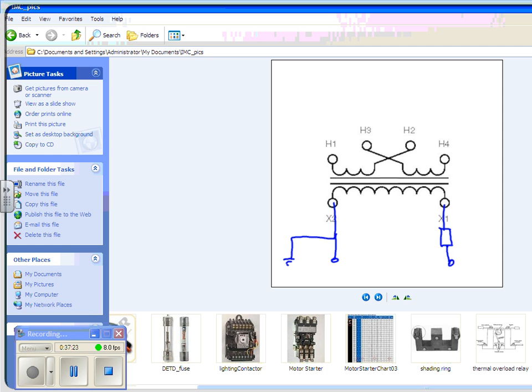And then we have what's called separate control, and that's where we take, say, a 120 volt lighting circuit, when we bring it into our control panel or our starter circuit, and we use that 120 volt independent circuit. Now it's fused from someplace else, completely different. So you might have your power off, but you might have a live control circuit. So you've got to be careful with that also. The one most safe, in my opinion, is the control transformer.